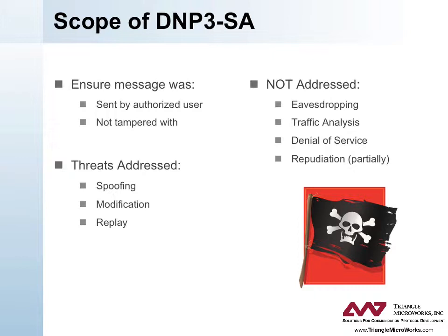To protect against such an attack, DNP3 Secure Authentication includes information in each message that changes each time a message is sent. DNP3 Secure Authentication can also help to protect against the threat of repudiation — that is, a valid user claiming not to have performed an incorrect or illegal operation. Although logging is not part of the specification, the authentication mechanism gives the remote device the necessary information to store a permanent log of who performed what operations, providing some degree of non-repudiation.